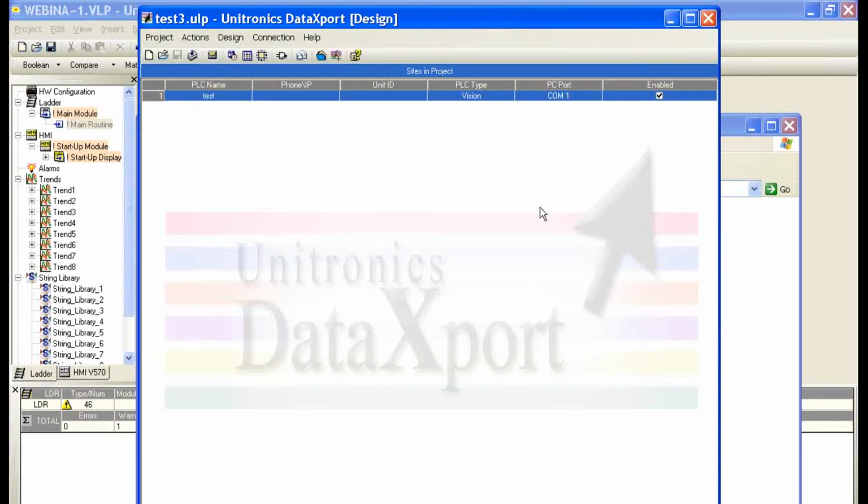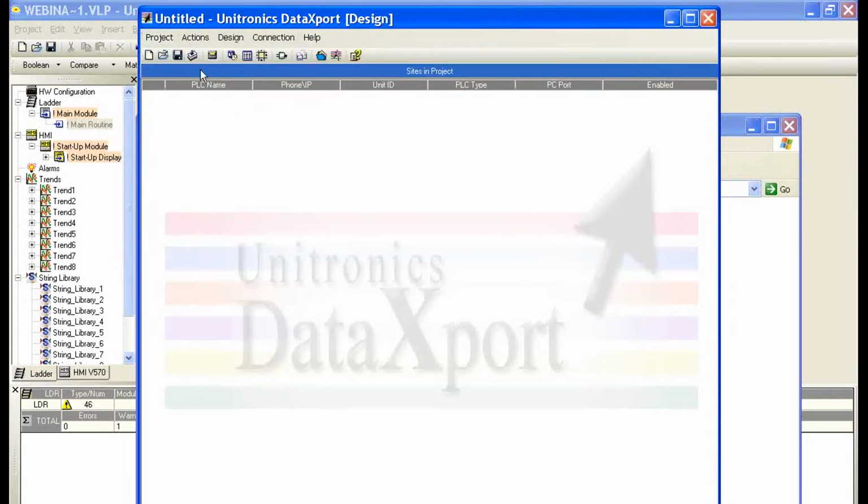And again, the only option we have over our serial connection here is to use a schedule or manually come and download. So one nice option we have over Ethernet is to perform a TCP/IP connect from the controller to the PC. So we're going to leave the PC in listen mode to start the download. So let's go ahead, and I'm going to create a new project. And this time we'll see how to perform a TCP/IP connect to do this.